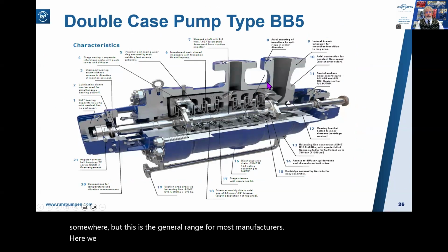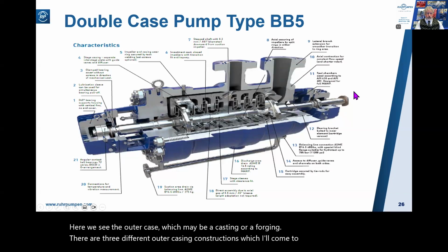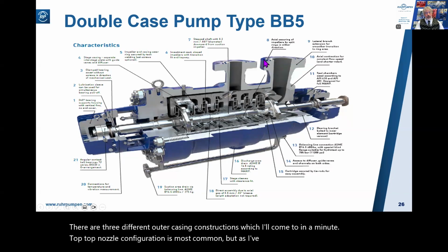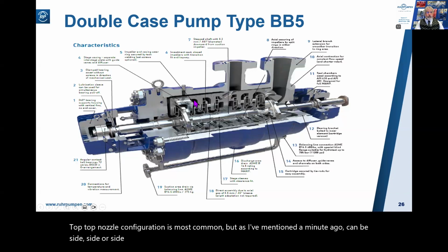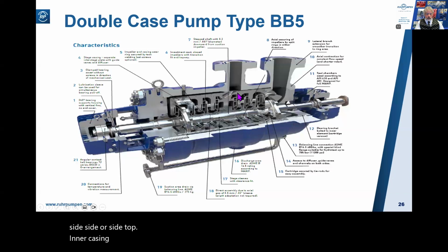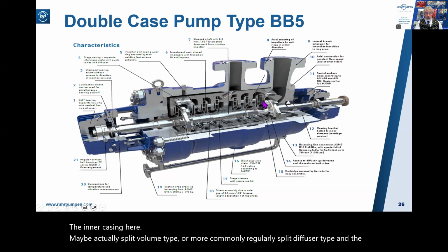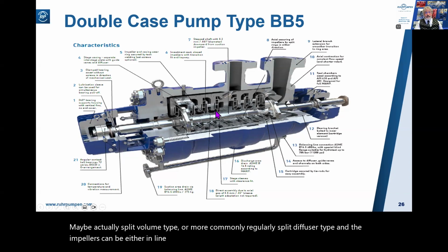Here we see the outer case, which may be a casting or a forging. There are three different outer casing constructions, which I'll come to in a minute. Top nozzle configuration is most common, but as I mentioned a minute ago, can be side or side top. The inner casing here may be axially split volute type, or more commonly, radially split diffuser type. And the impellers can be either in line, all facing the same direction, or as shown here, back to back.